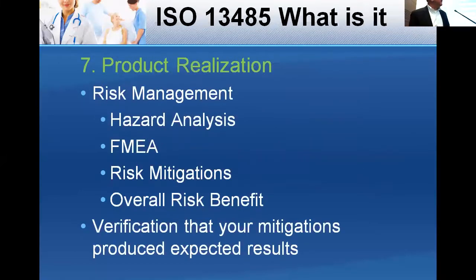Product realization. Risk management, as I said, the risk file is a really big part of this standard and becoming more and more important as we understand its value more. There are several risk management methods. It's really great to start with a hazard analysis because hazard analysis is relatively high level. You're looking at 5 or 6 to 8 things that you can focus on. What are the hazards related to your product, and find mitigations for those hazards.